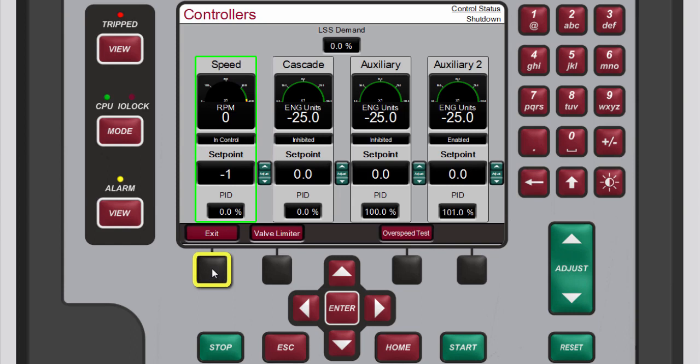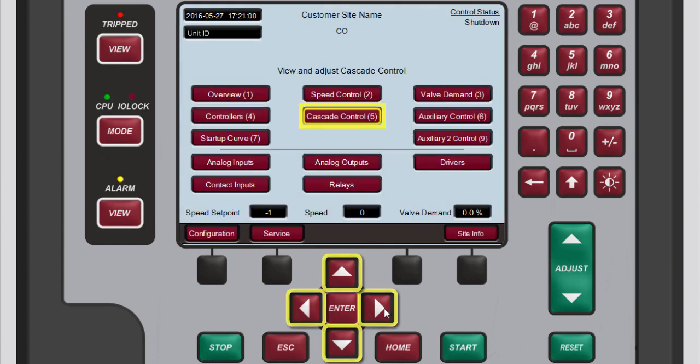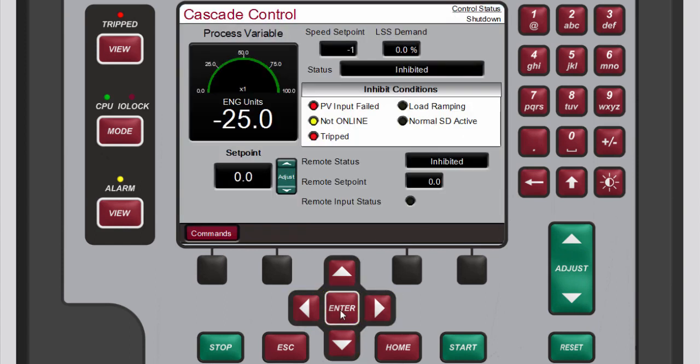The cascade control screen is available when the unit is configured for cascade control. This screen provides details related to the cascade control loop. The cascade control output determines the setpoint for the speed control, which allows the 505 to vary the speed control setpoint as it relates to another process variable selected by the user.